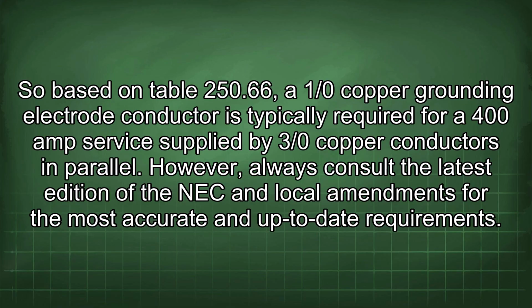So based on Table 250.66, a 1/0 copper grounding electrode conductor is typically required for a 400 amp service supplied by 3/0 copper conductors in parallel. However, always consult the latest edition of the NEC and local amendments for the most accurate and up-to-date requirements.